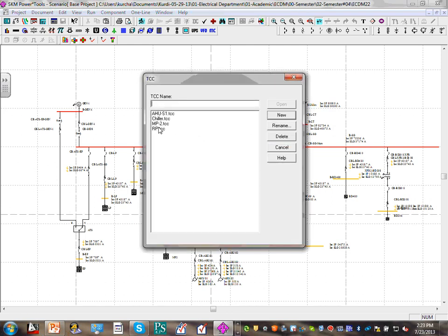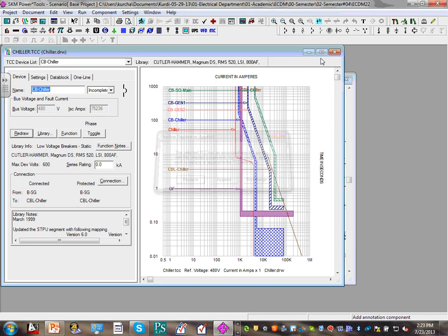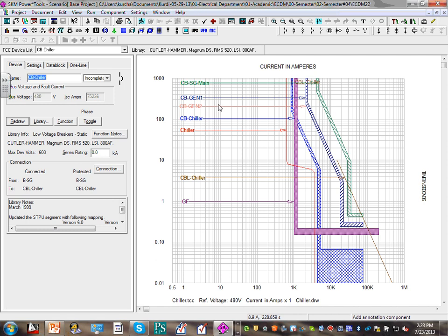So here's a TCC that I ran. This is a chiller, just directly to a chiller coordination. Feel free to jump in, guys. So I have my main at the top right here. I disabled the instantaneous on my main, assuming you can see my main instantaneous.